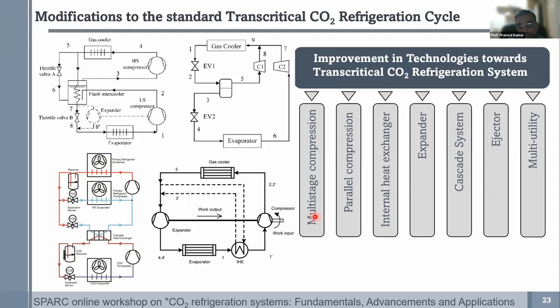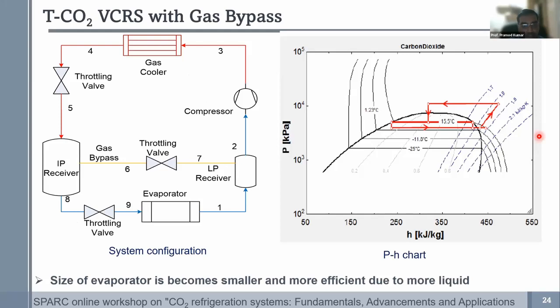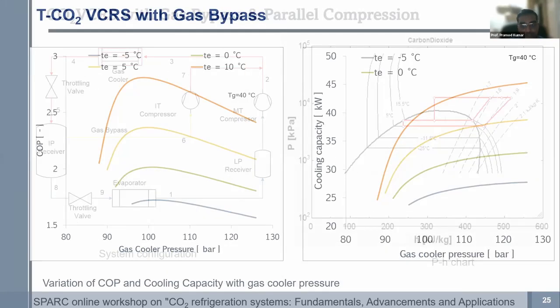These are the current technologies that are available with transcritical CO2 systems. You have multi-stage compression, parallel compression, and internal heat exchangers, and the expander is certainly being looked into. You can go for cascade systems, you can look at the ejector, and you can look at a multi-utility system with different slabs of evaporation temperatures to produce different kinds of cooling and heating requirements. Professor Maiya has mentioned this in great detail, so I'll not go deeper into it.